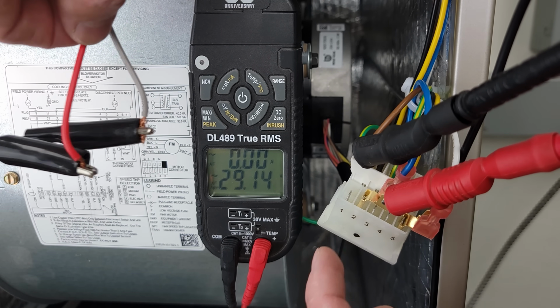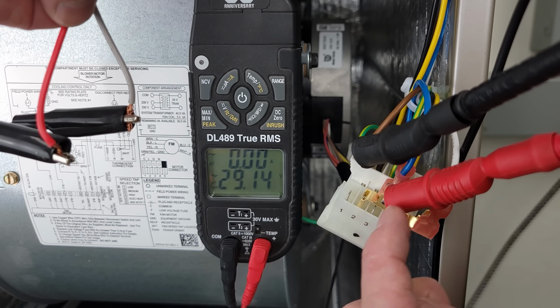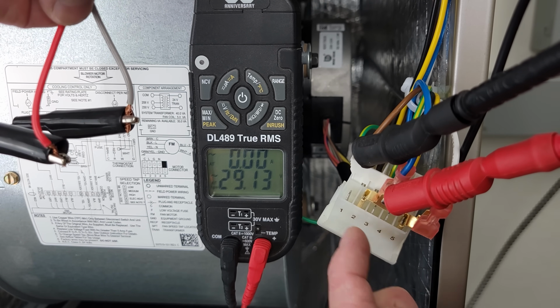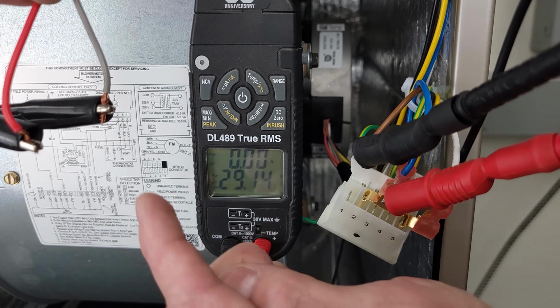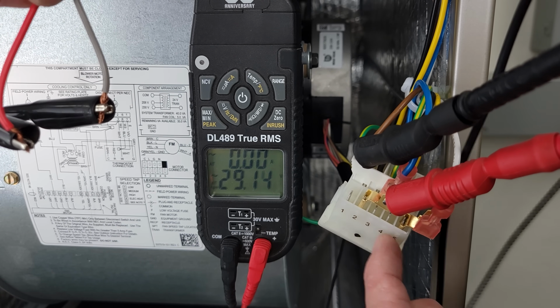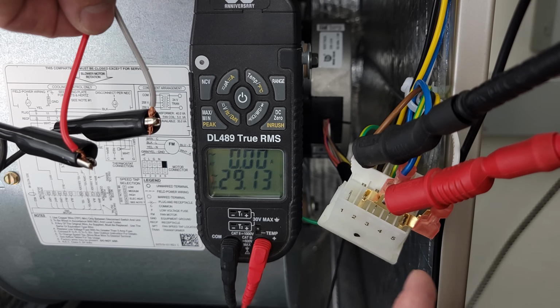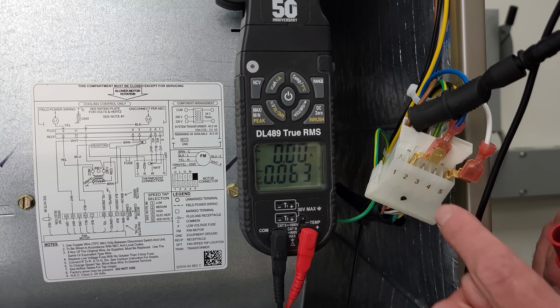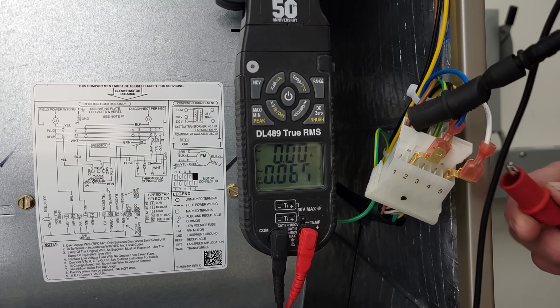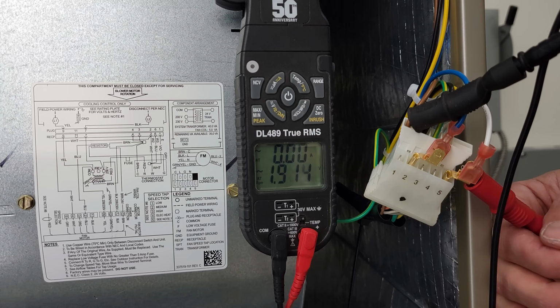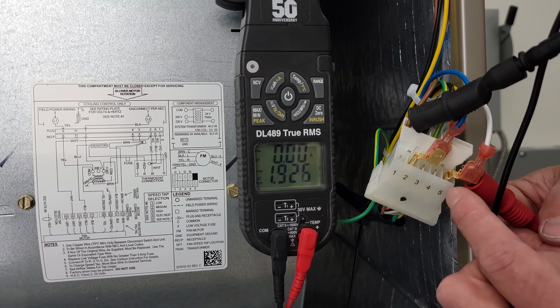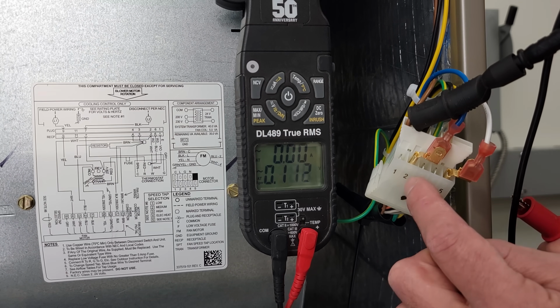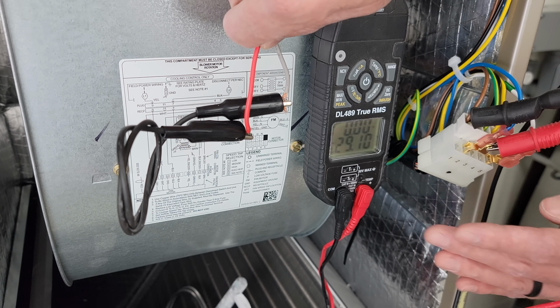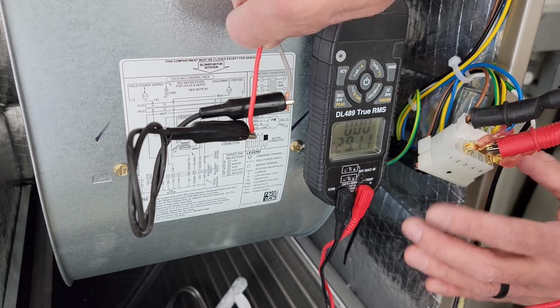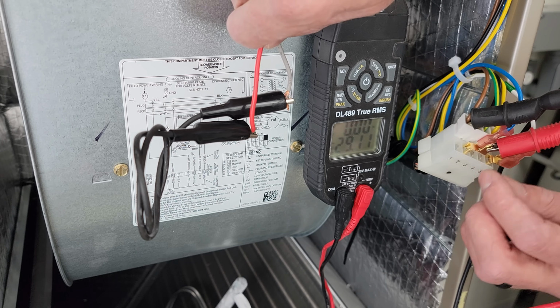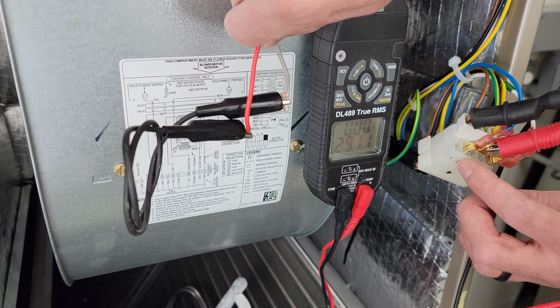And so the thing is, what you could do is you could also take this powered Spade terminal and go into each one of these numbered connectors and see if it's going to turn on. Maybe one of these numbers was not programmed by the factory, and that's the issue. And so we know number 2 is being powered. If this was not being powered, you could also put your probe on number 5 and check for voltage there. In this case, you can see that the number 5 speed is not being powered, only number 2 is. But since you see that the blower motor is running, you know that this one's good. It really is that simple. Do you have power to the plug? And do you have your 24 volt signal selecting which speed it's supposed to turn on at?